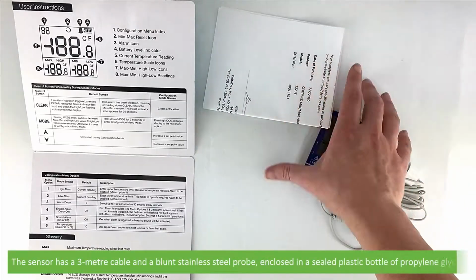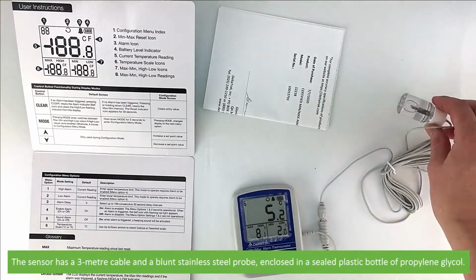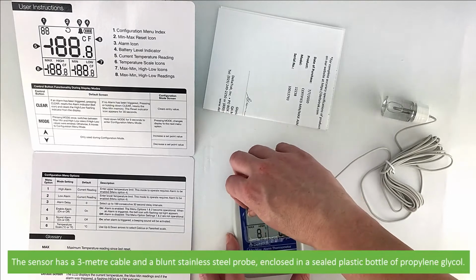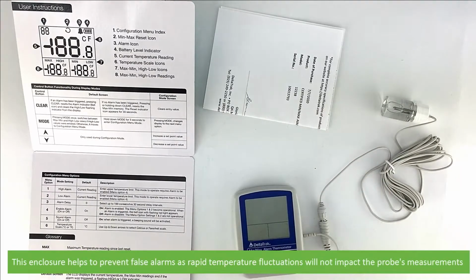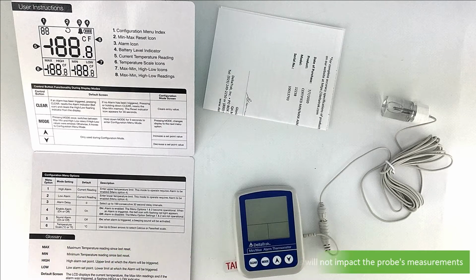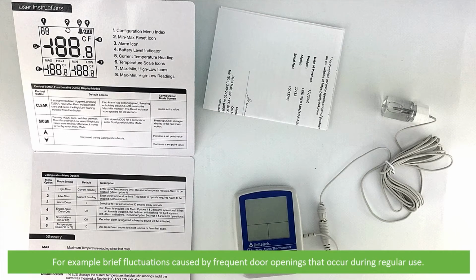The sensor has a 3-meter cable and a blunt stainless steel probe enclosed in a sealed plastic bottle of propylene glycol. This enclosure helps prevent false alarms, as rapid temperature fluctuations will not impact the probe's measurements, for example brief fluctuations caused by frequent door openings that occur during regular use.